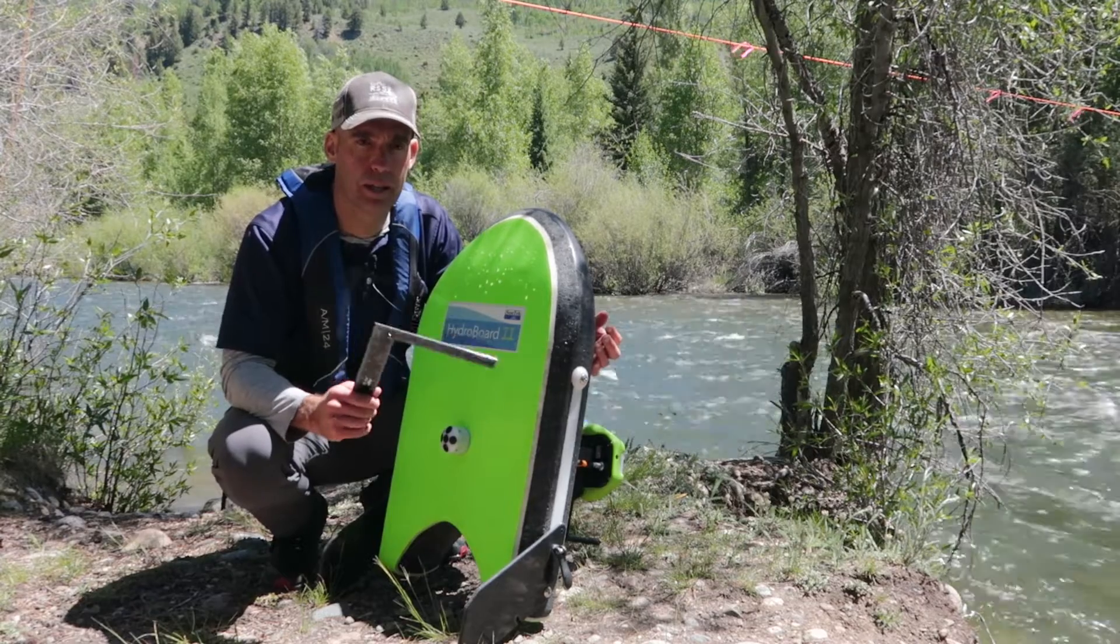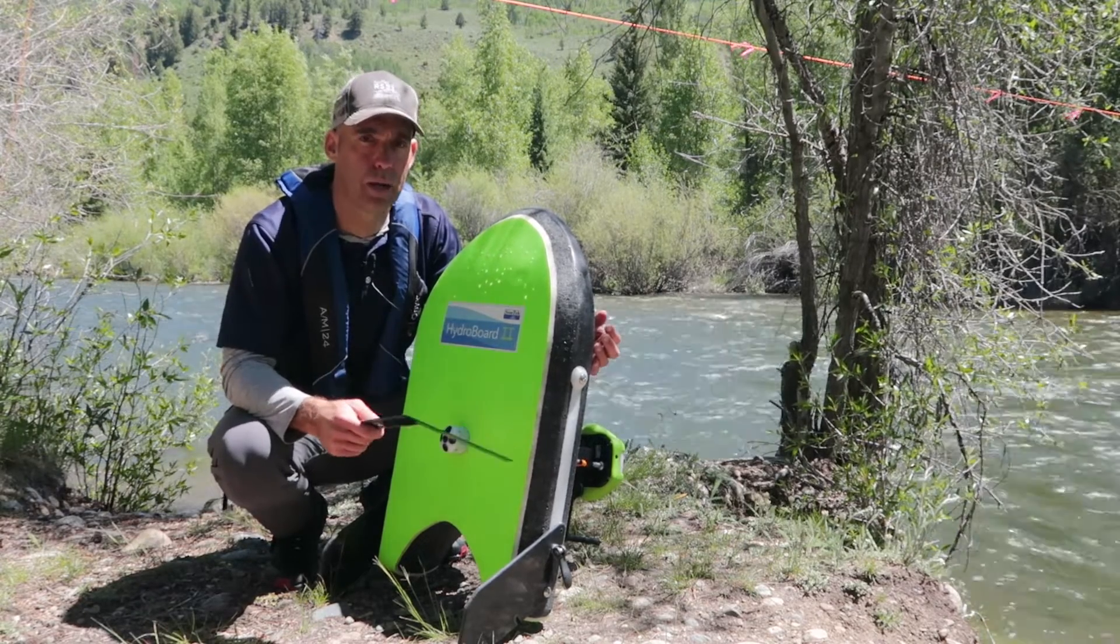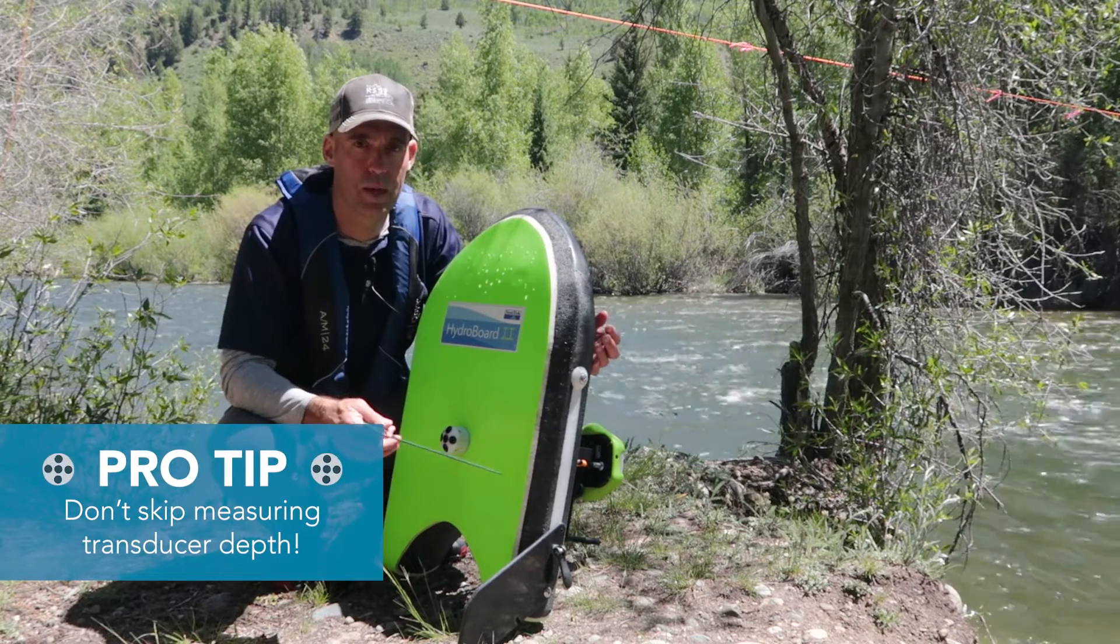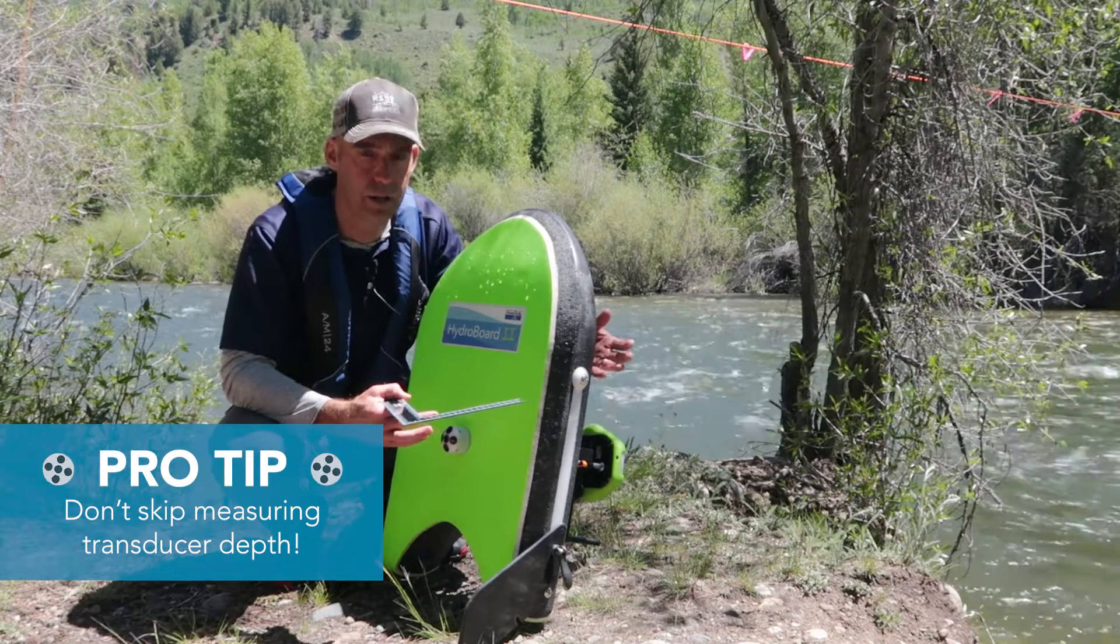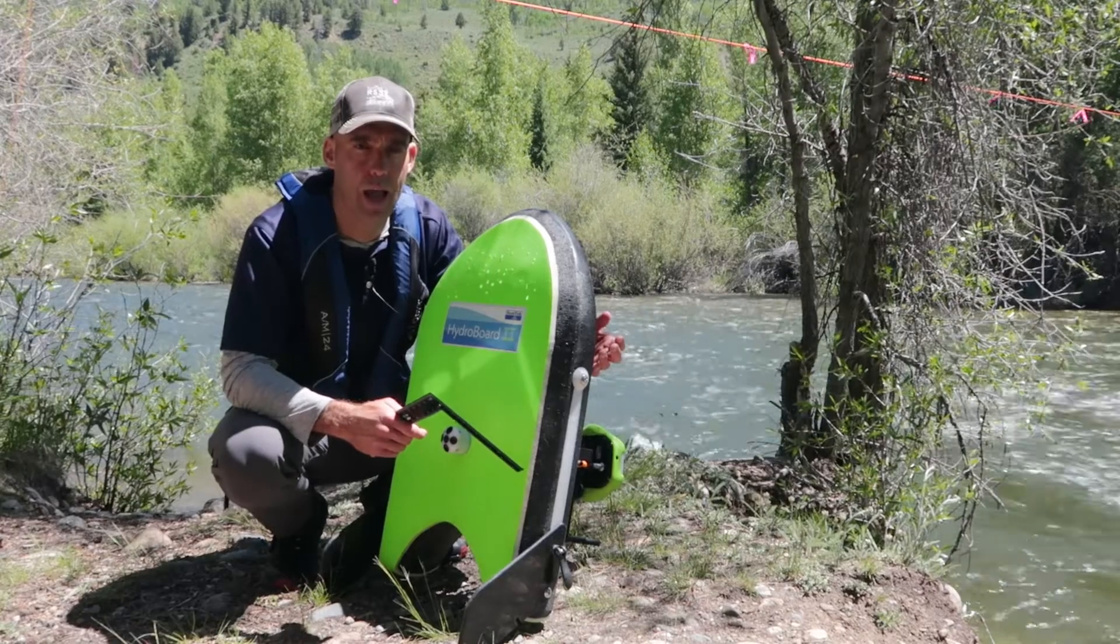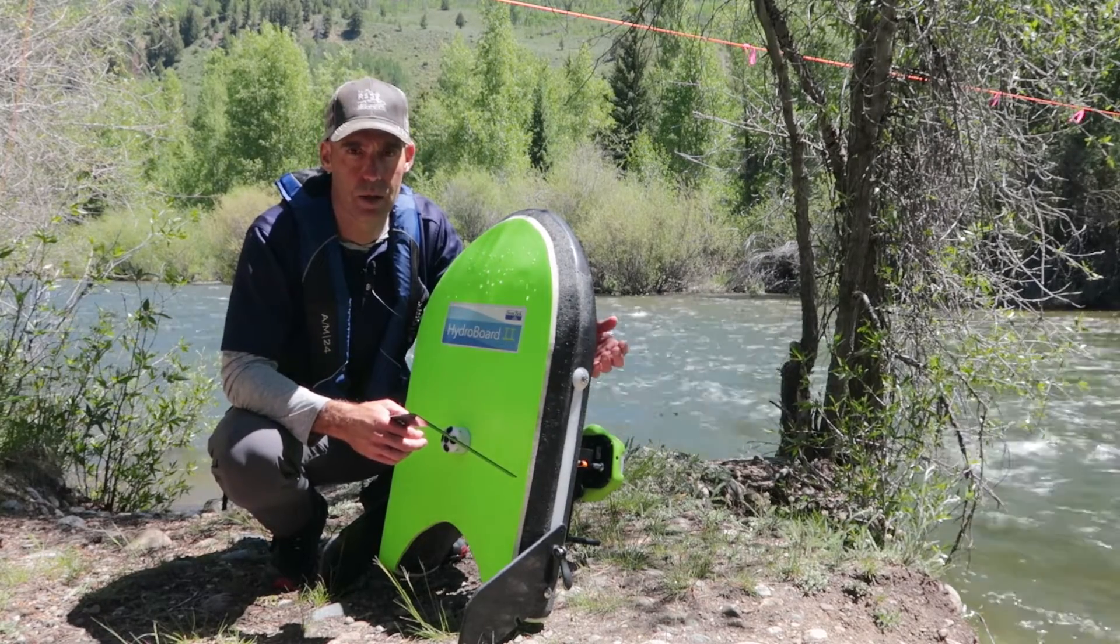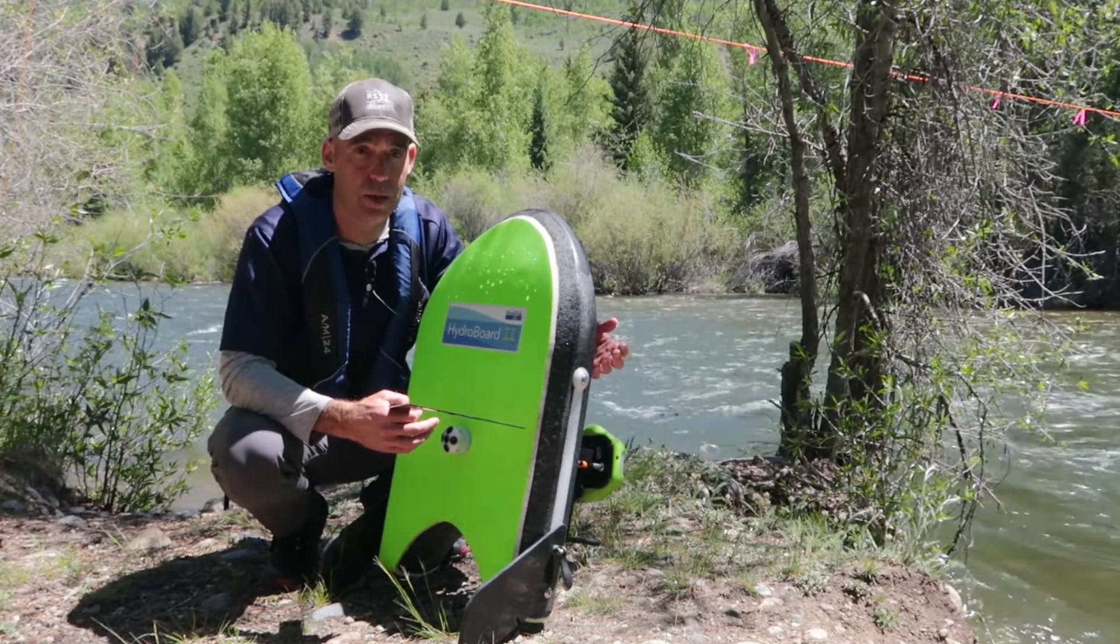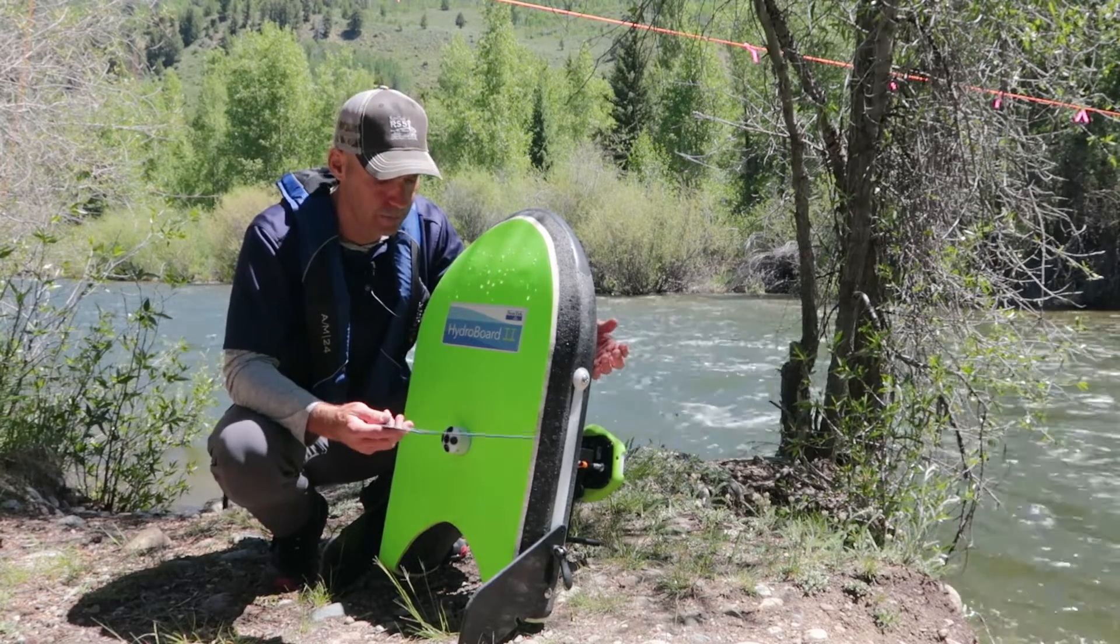Some people ballpark this or estimate this, which we definitely do not recommend because an accurate transducer depth leads to an accurate discharge measurement. That's because this transducer depth is factored into the final discharge. It gets calculated into the area and the discharge is the area times the velocity. So if we have an inaccurate transducer depth, depending on how wide our channel is, we could have quite a big error in our total area for our site.